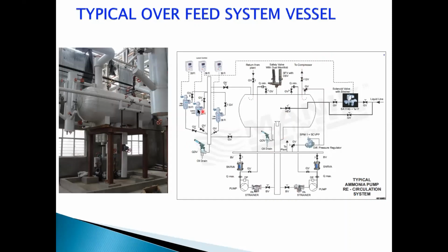Here normally we use either a level transmitter and high-low level float switches, or you use 3-level switches. The function of this level controller, the center one, is to control the on-off of the solenoid valve. The second one is to maintain a minimum level in the low pressure receiver. And the third one is to protect against surges of liquid into the ammonia compressor. So this can be a high level trip, this is a low level trip, and this is a control device.